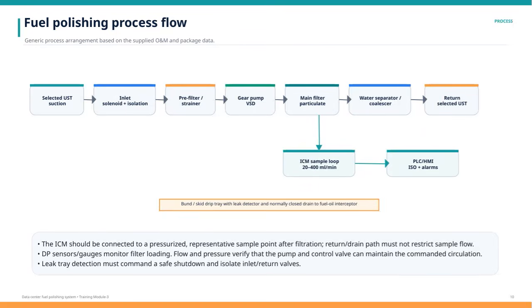Let's walk through the fuel polishing process flow shown here. This is a generic arrangement based on the operation and maintenance data, along with package specifications. We start with the selected underground storage tank suction point, where fuel is drawn into the system. Next, the fuel passes through an inlet solenoid valve combined with an isolation valve, allowing for controlled entry and the ability to isolate the system when needed.